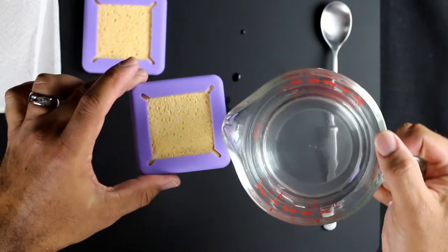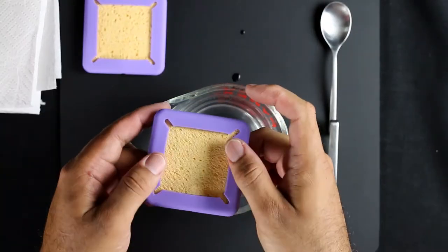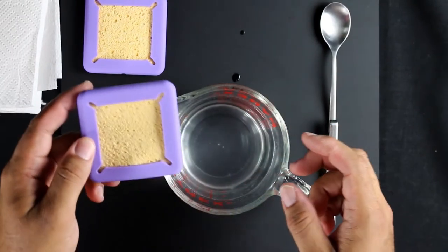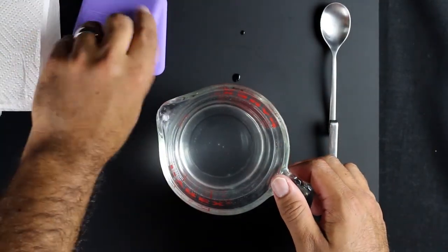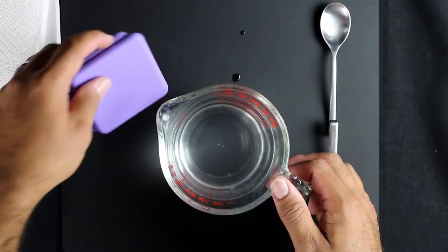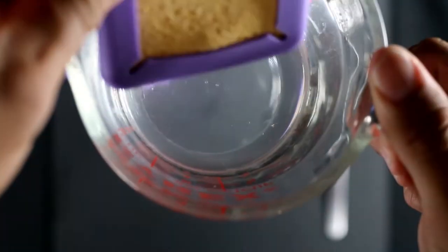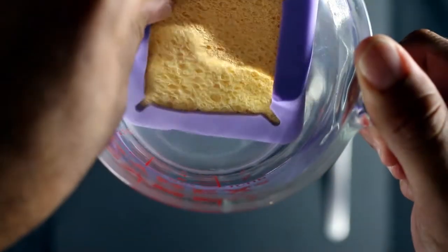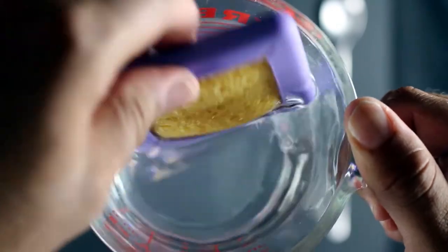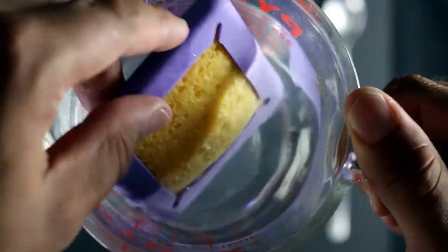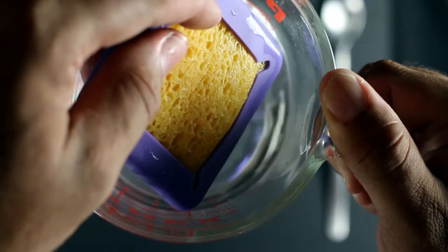I could just go ahead and pour these electrodes over a sink and get them soaked enough, but it won't do for this particular setting. So if you want to use an open container, that's also a very good idea. Make sure the electrodes are soaked enough in water. So when you insert them in saline solution, what's going to happen is the sponge insert, the cellulose insert, is going to soak up.